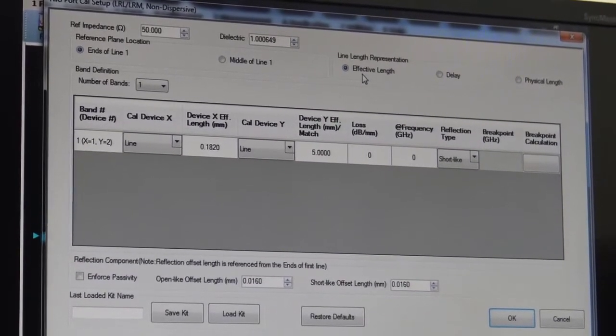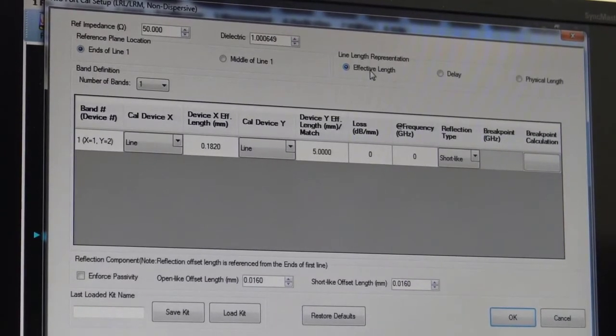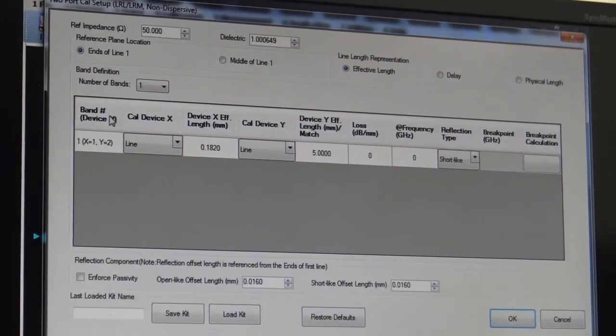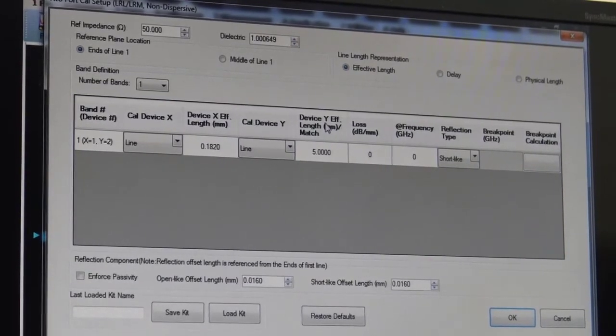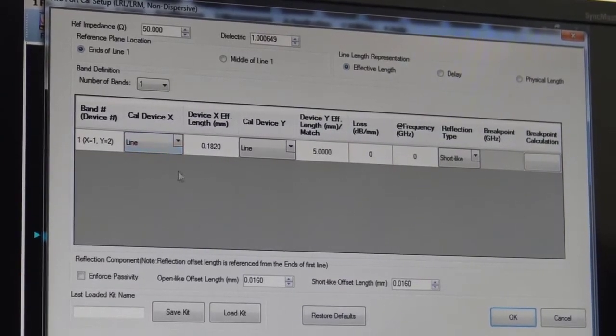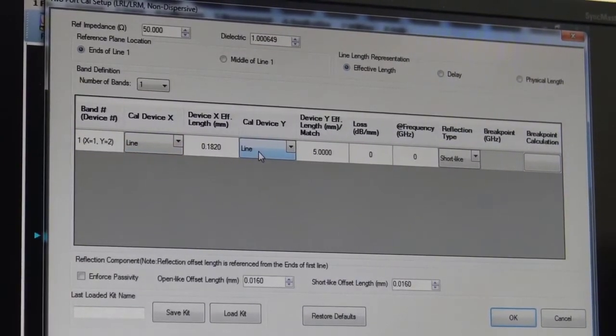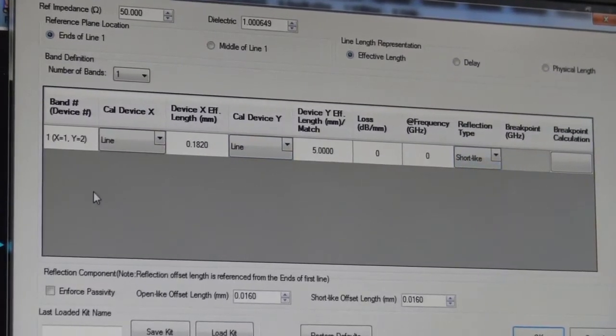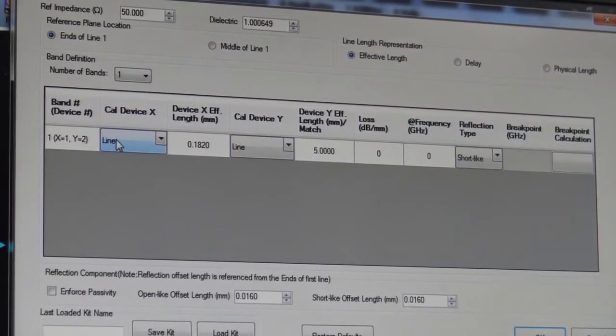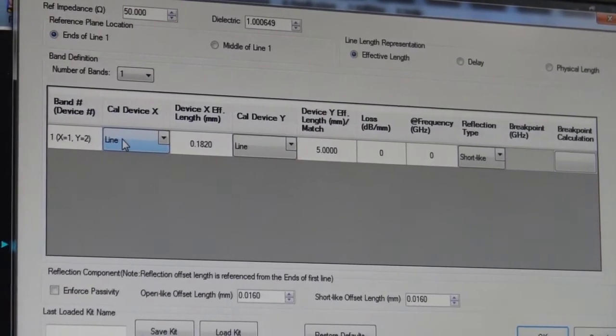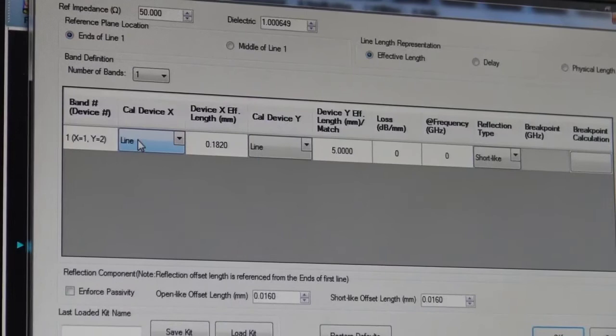And we have selected effective length in this representation. And then down here is where we define the number of bands we'll be using and the types of devices. So if this were LRL, then we would have two lines, a line and a second line, and then a reflect. So our first line is our calibration through, and it's 182 micron length, effective length, and that's what's entered here.